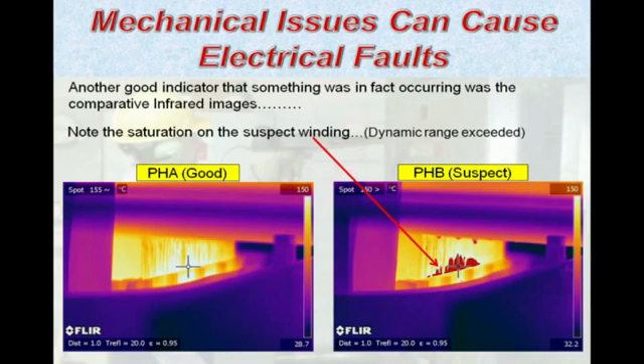Now, another indicator that we found pointed to something going on was the infrared image. Everybody's familiar with infrared. It's a great complementary tool, widely used. And looking at the left side, what I call the good transformer, this is the horizontal core piece coming up through the winding, and you'll notice it's measuring a temperature of approximately 155, which is not uncommon for these core temperatures to run higher. But you'll notice on what I call the suspect coil, the dynamic range of the camera is exceeded. It's greater than 150 degrees C, and the camera can't quantify that. You'll also see there's some saturation in this image showing where the temperatures are higher than the camera can measure.